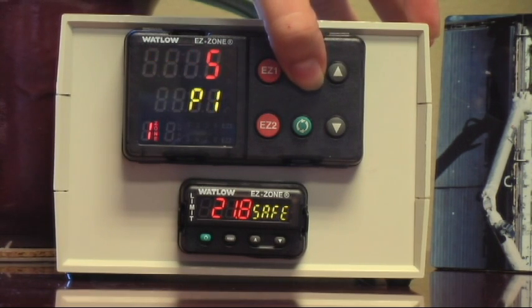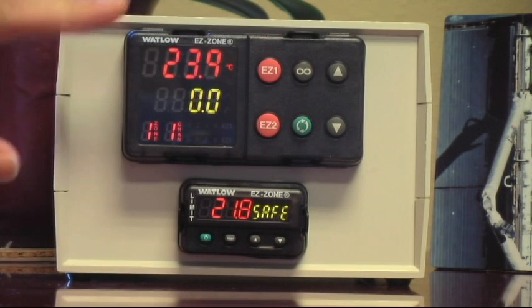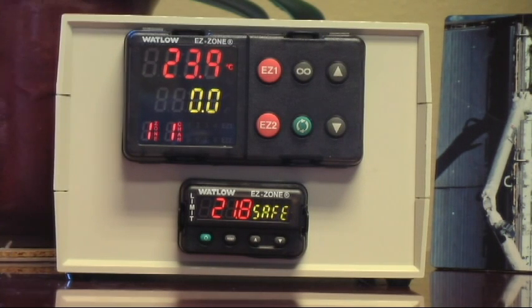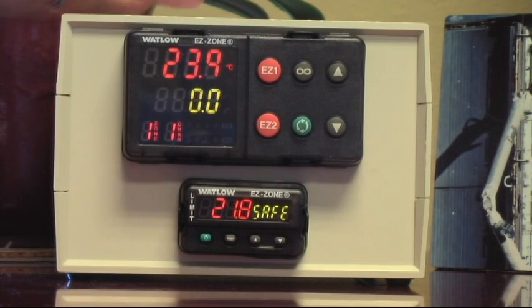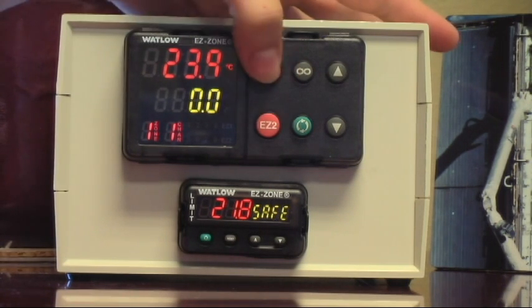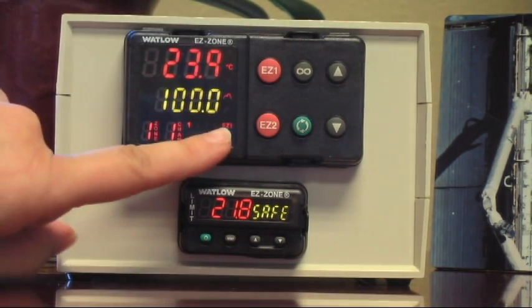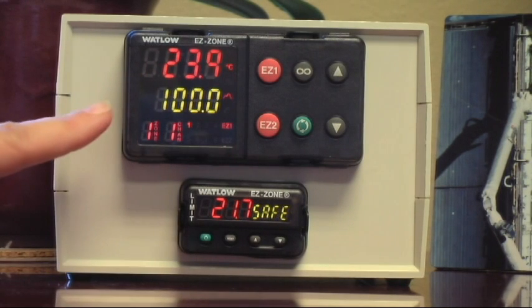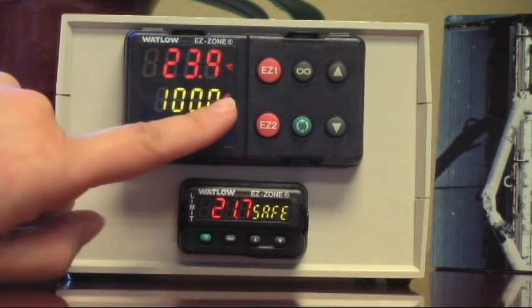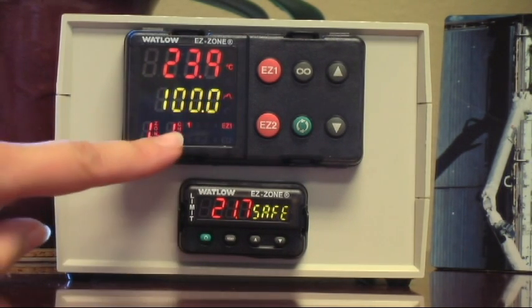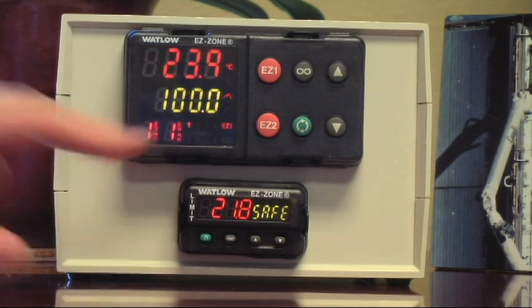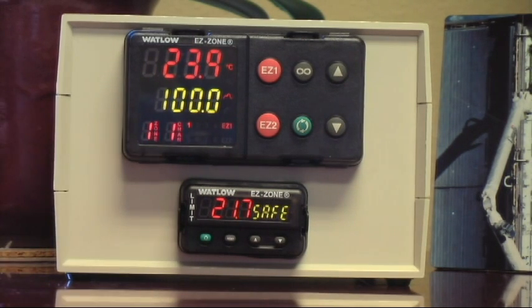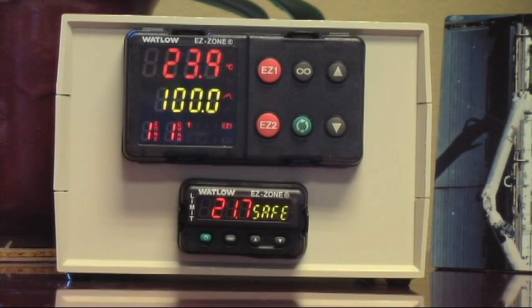So to get back to the menu, we'll just hold the infinity key. We're back to the menu. And just to show that this works, we'll press EZ1, because that was our profile for EZ1. And let's see what happens. EZ1 starts. And right away, we say we're ramping to 100 degrees. And we're calling for full power to the heaters. Fantastic. We've achieved go to 100 degrees and soak for eight hours.